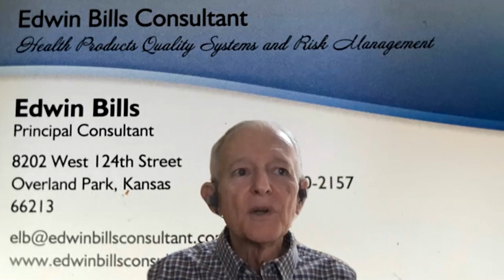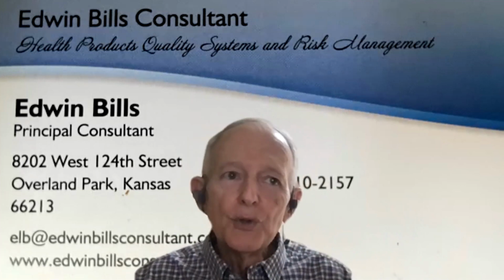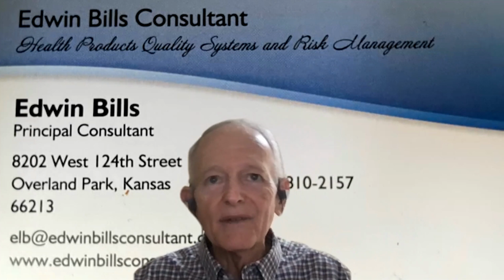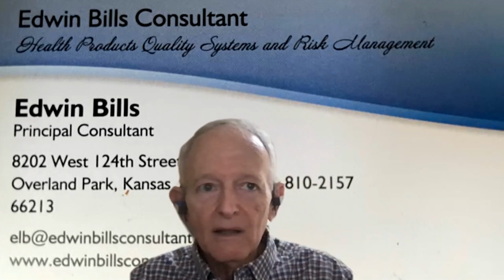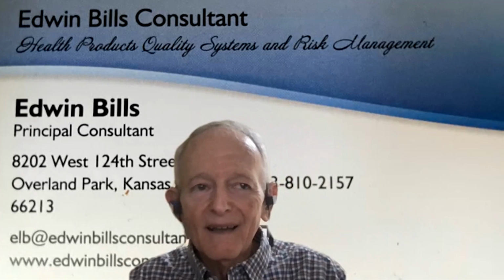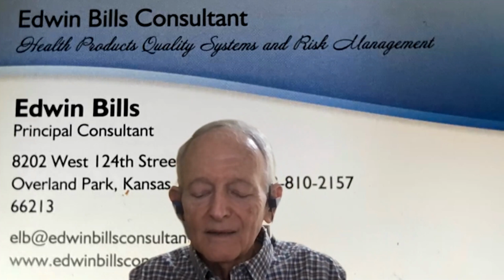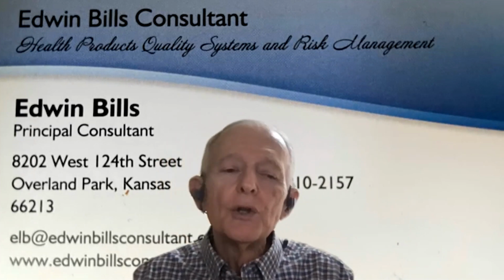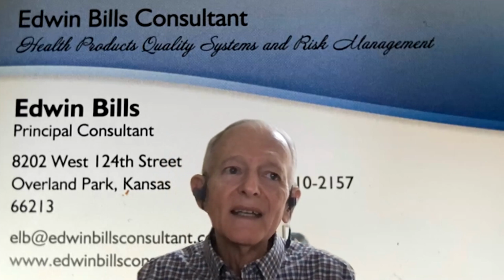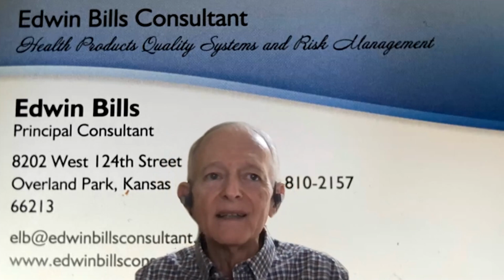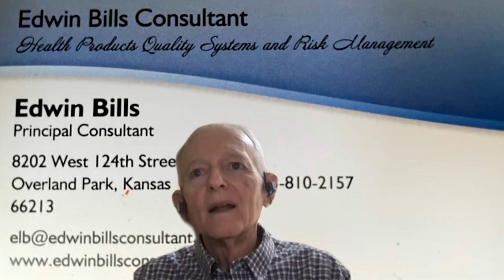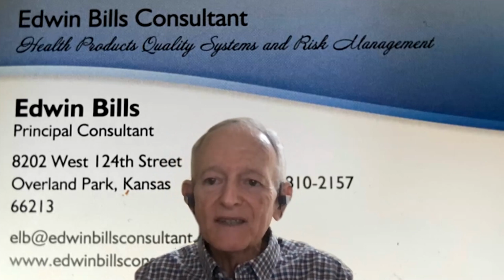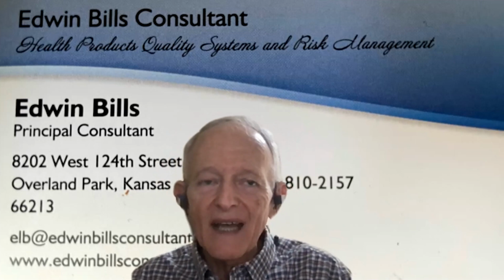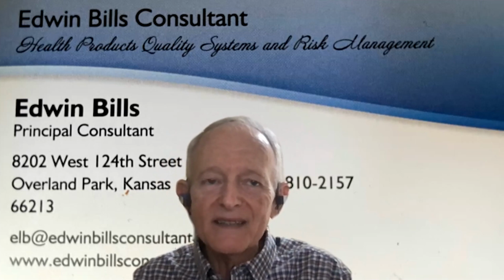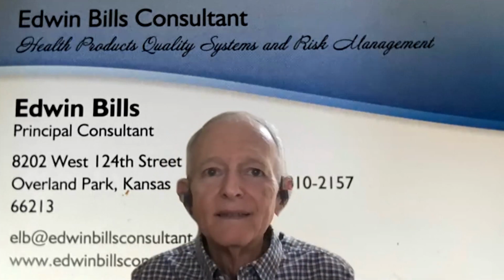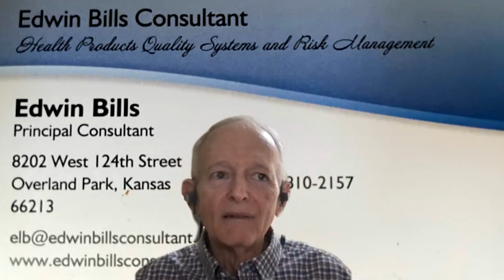And then if there's a risk control identified and you use that particular risk control identified in the standard, you don't have to do the evaluation; you just put that in as a safety requirement in the design input phase. And then if you use the verification testing that's identified in the standard and get the results that are prescribed in the standard, then you're done. The risk now is acceptable.